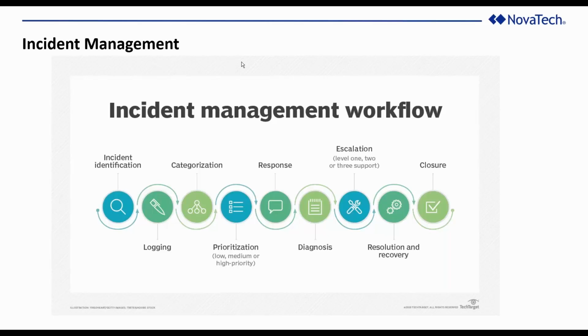With the diagnosis, the OT personnel could look at the logs on the web server SCADA and the field Orion RTU to find the issue. In this particular example, they don't see a record of a control being issued on the RTU. So they check the communication logs for the web server SCADA system and notice that on the devices screen, the percent successful is slowly decreasing, indicating an intermittent comms fault.